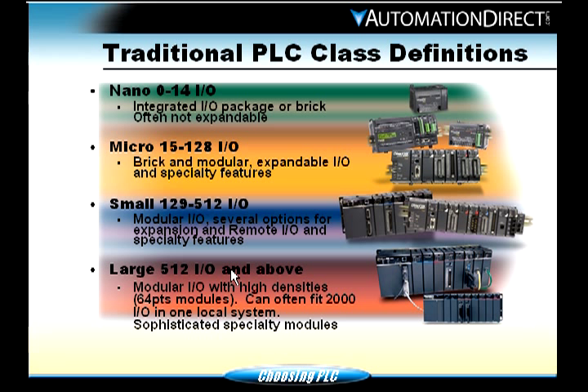The classes of PLCs: Nano PLCs have 0 to 14 inputs and outputs — I/O being your connection to the real world with devices. Nanos have 0 to 14 integrated I/O and are often not expandable, though our DL05 is a Nano that does have one expansion slot. Micro PLCs range from 15 I/O up to 128 and can be brick or modular — our DL06 falls in this class. Small PLCs go from 129 to 512 I/O, with expansion, remote I/O, and a lot of specialty cards available.